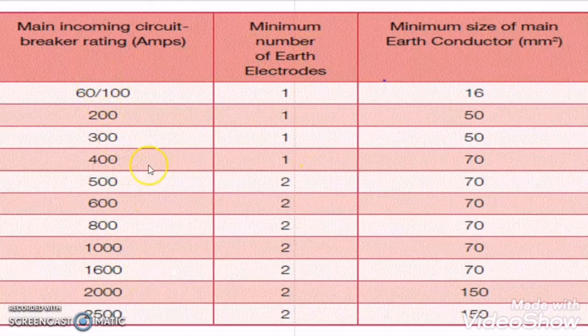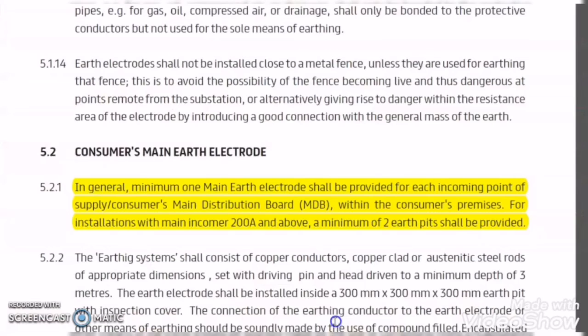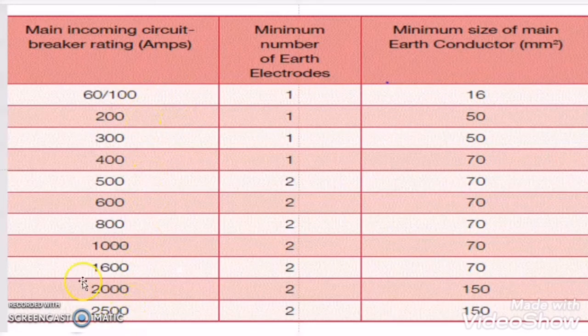In DEWA and ADDC regulation, the size of the conductor will be the same as per the breaker rating, but the number of earth pits will change. As per the ADDC regulation, two pits are required when the incomer rating is 500 ampere and above. But for the DEWA regulation, after 200 ampere of the main incomer rating, two earth pits are required. However, the cable size in both ADDC and DEWA regulation will be selected the same as per this chart.